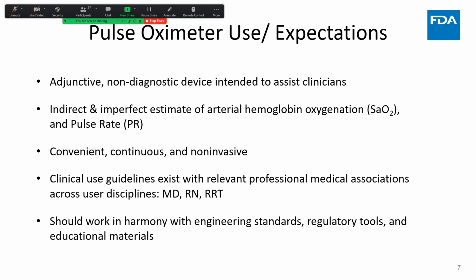Now, the first one is you would sample a direct blood specimen. That is common practice, but bear in mind that it really emphasizes the point that this is a non-diagnostic device, in spite of the fact that some societies have taken it on to actually put hard numbers on where intervention or care thresholds are established. That is outside of our conversation here, but it is certainly something a bit worrisome for a device that was never intended to be a direct measure of oxygenated hemoglobin.